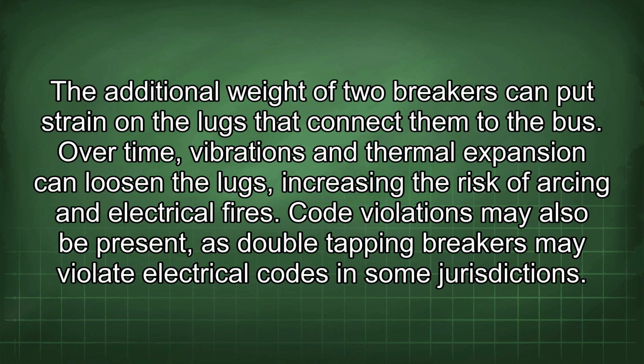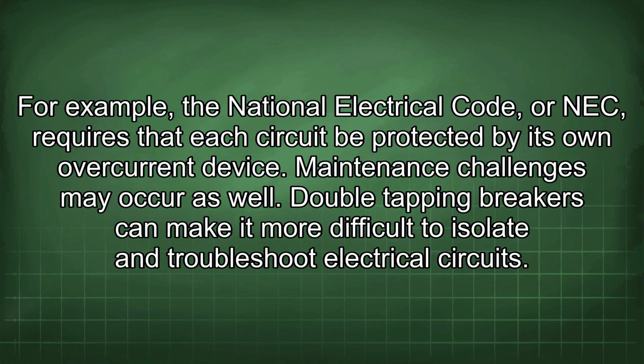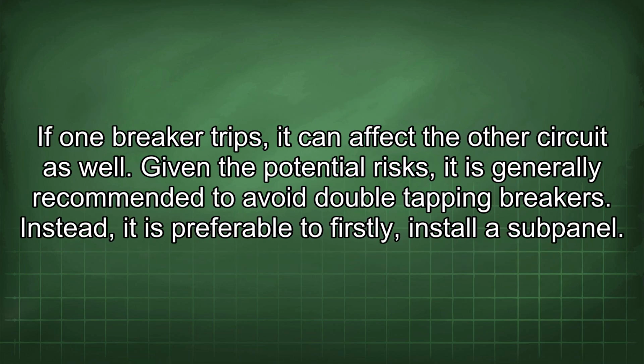Code violations may also be present, as double tapping breakers may violate electrical codes in some jurisdictions. For example, the National Electrical Code, or NEC, requires that each circuit be protected by its own overcurrent device. Maintenance challenges may occur as well. Double tapping breakers can make it more difficult to isolate and troubleshoot electrical circuits. If one breaker trips, it can affect the other circuit as well.